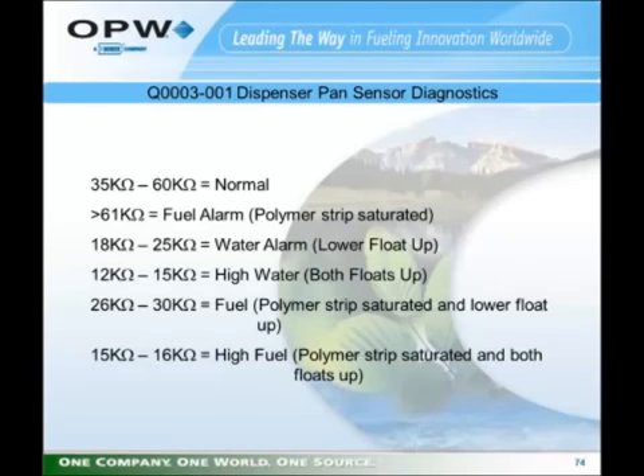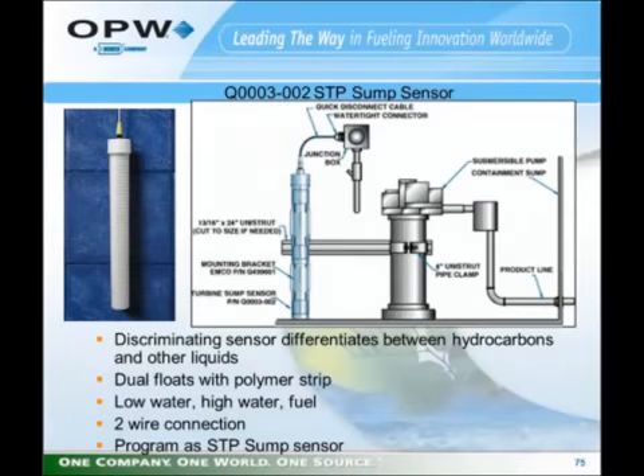For diagnostics on the dispenser pan sensor, we've given you a listing of resistance readings for that sensor that indicate different states that the sensor might be in: normal, fuel alarm, water alarm. You could use these readings for troubleshooting sensor operation.